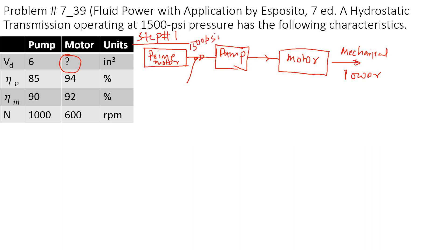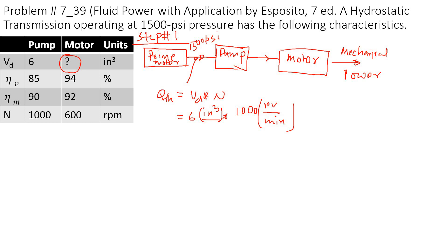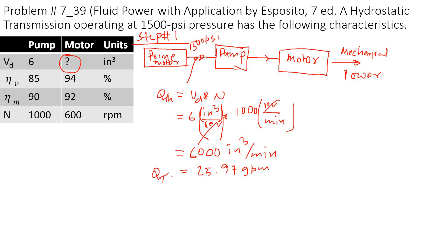We can calculate the theoretical flow produced by the pump. The theoretical flow equals the volumetric displacement times RPM. The volumetric displacement is 6 in³ and the pump speed is 1000 RPM. Typically, volumetric displacement is per revolution, but you can include that unit so it cancels out. That gives 6000 in³/min, which equals 25.97 gallons per minute — that's the theoretical pump flow.